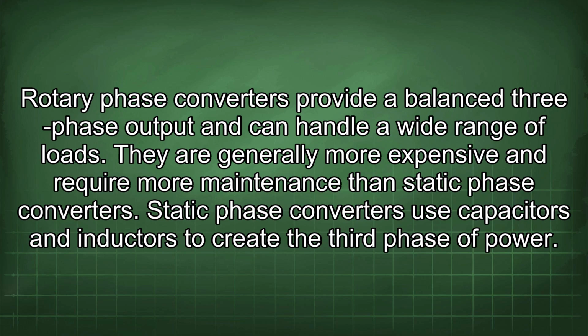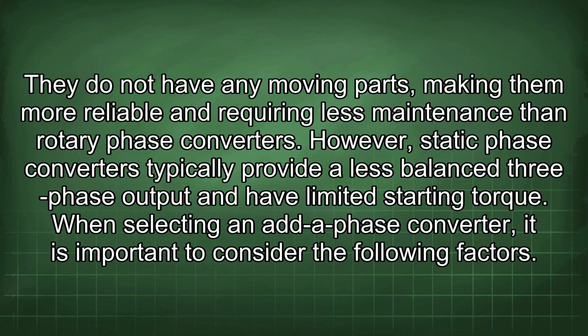Static phase converters use capacitors and inductors to create the third phase of power. They do not have any moving parts, making them more reliable and requiring less maintenance than rotary phase converters. However, static phase converters typically provide a less balanced three-phase output and have limited starting torque.